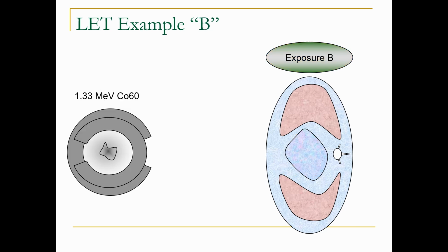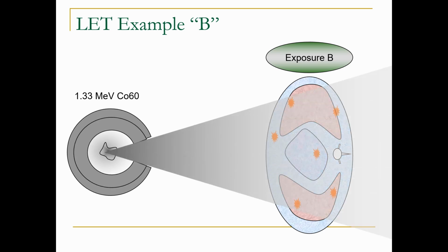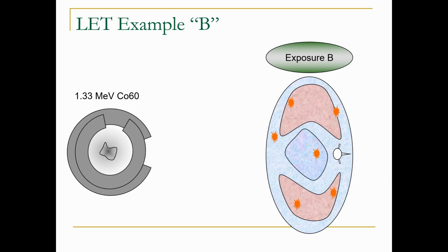This slide depicts a mass of cobalt-60 held inside a lead enclosure. Cobalt-60 emits a couple of gamma rays, one at 1.17 and the other at 1.33 mega-electron volts. Rotating the inner shield exposes the cobalt, and the patient is exposed to the radiation as in a therapy treatment. Rotating the inner shield back to its home position stops the radiation exposure to the patient's tissues. Notice the pattern of ionization effects in the patient's anatomy.